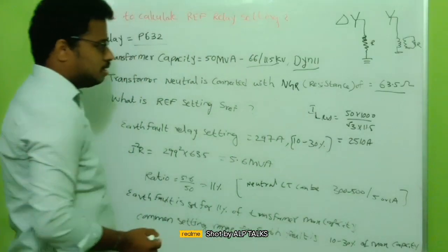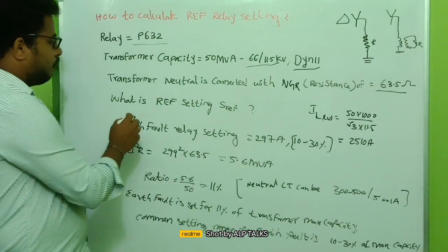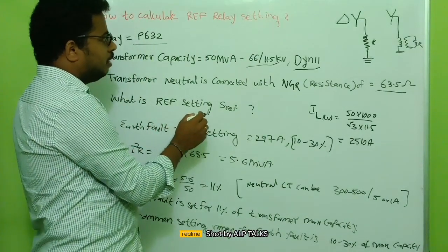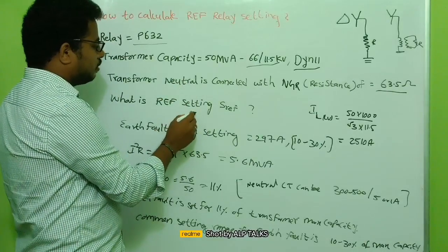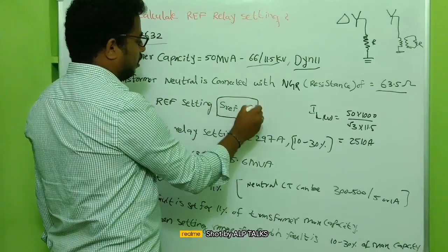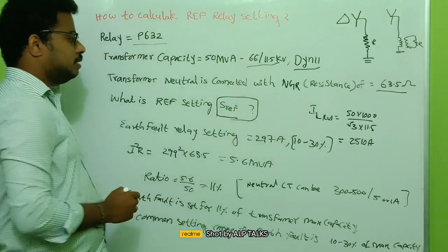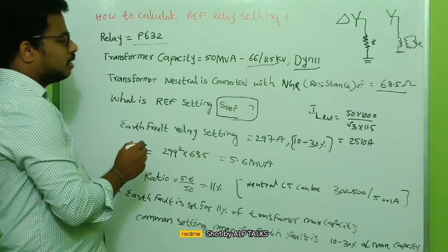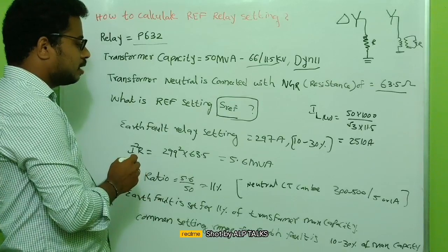So the resistance is 63.5 ohm. What is the REF setting? In a REF relay we have to set the power, the apparent power, the entire apparent power we have to set as the reference power. What is the reference power and what is the current?